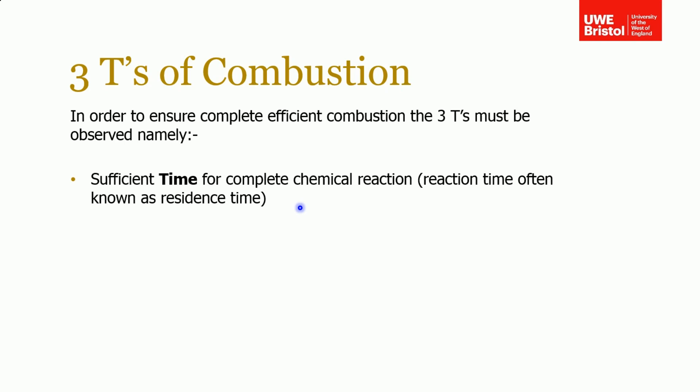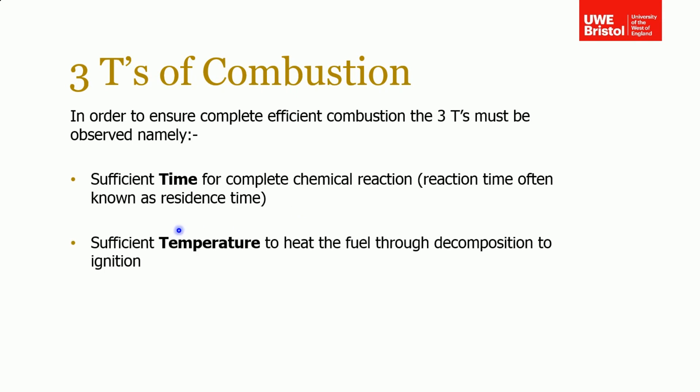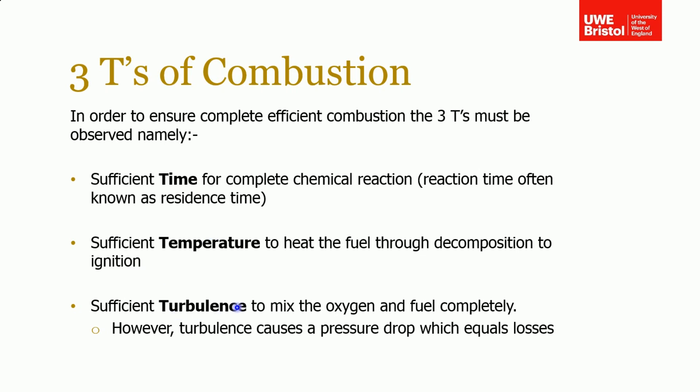You also need sufficient temperature — basically to heat the fuel through to decomposition and ignition. The heat from the flame front breaks down the fuel ahead of it, which then reacts with the air, releasing more heat and sustaining combustion. Finally, you need sufficient turbulence — in other words, a good mix between oxygen and fuel. Pockets of pure fuel can't burn by themselves. Better mixing improves combustion efficiency, though turbulence often results in a pressure drop, creating a trade-off with system losses.